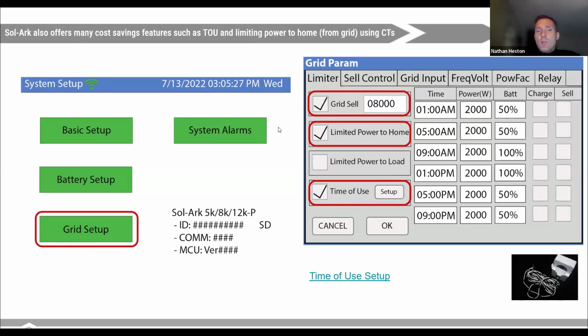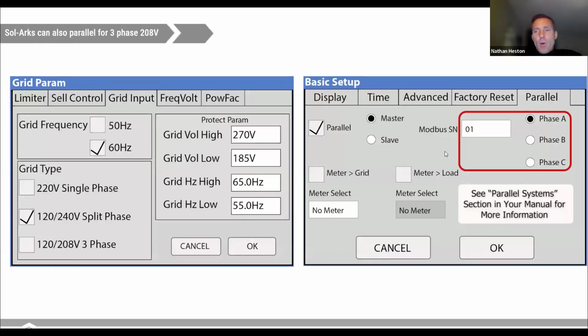based on the rates essentially, or the times that you want to use battery power to offset the pulling power from the grid. So this can be a very nice way, if you do have time of use rates, to either buy electricity when it's cheap or to charge up during the day and then discharge at specific rates throughout the night. I did point out that you can do 3-phase power by paralleling multiple inverters.